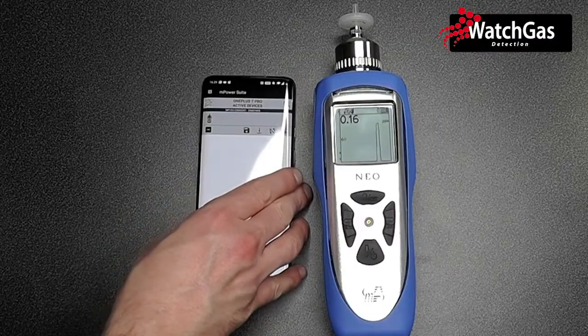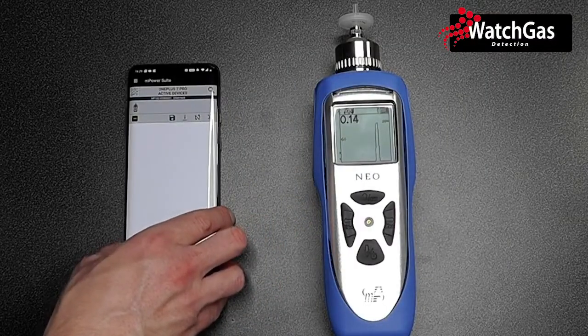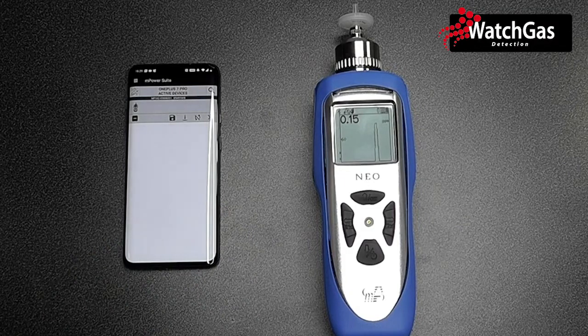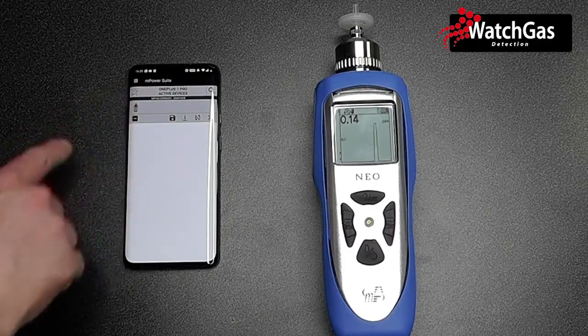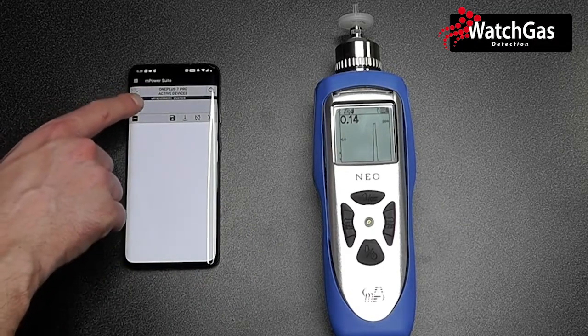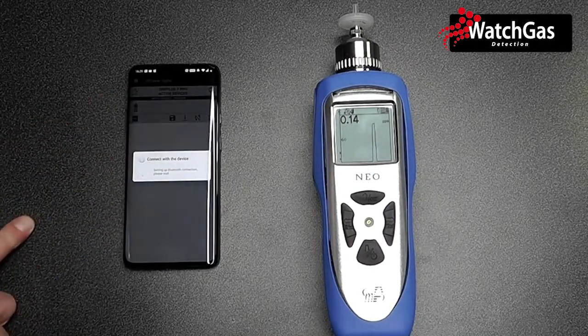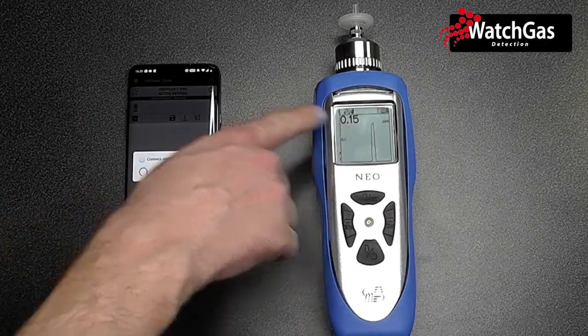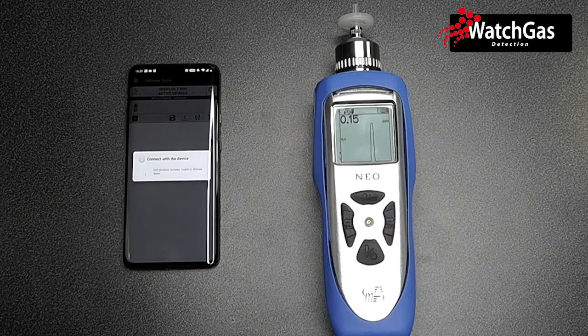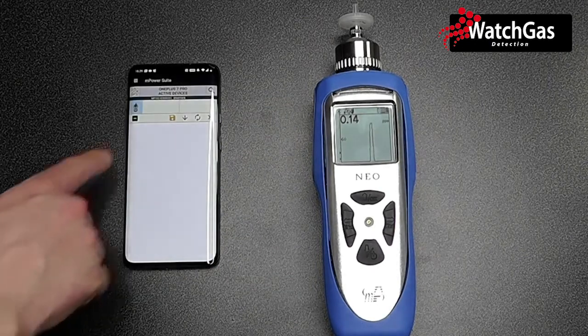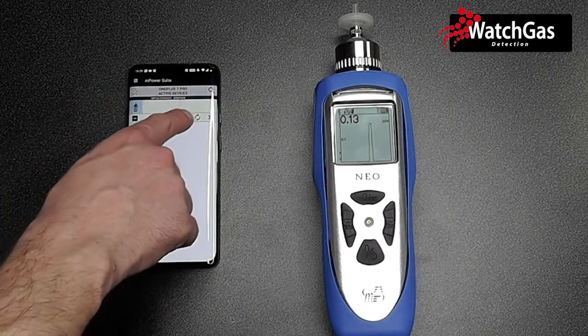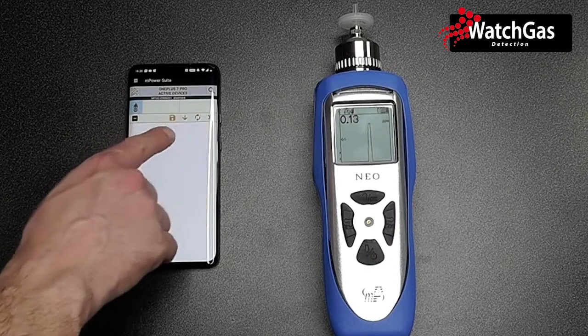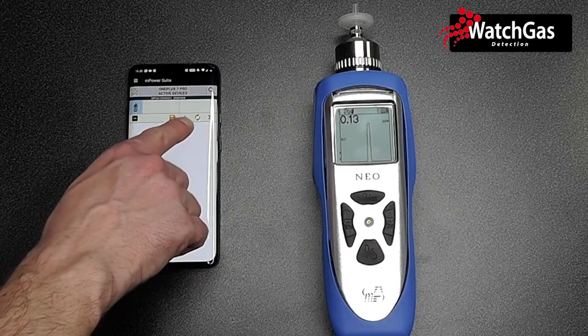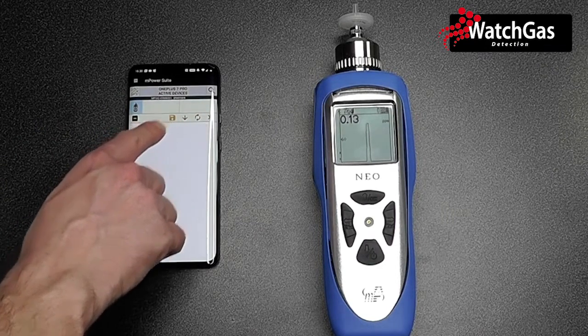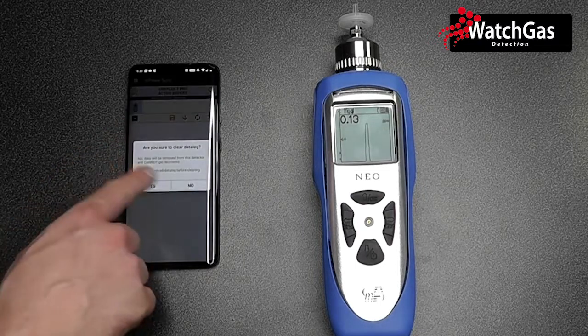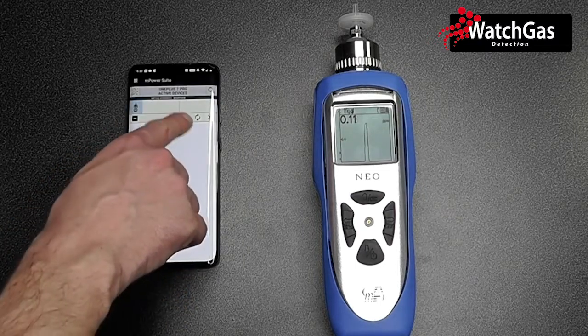Now, looking at the Bluetooth side of the instrument and the capabilities we have within the wireless communication, I have already connected on my particular device to this instrument, so if I press, this will now connect with our device live via Bluetooth, and I can see I'm now connected to the device. I can download any data logs, so by pressing the down arrow I can download any data logs. I can clear the data log settings by pressing that. I don't want to clear the data logs.